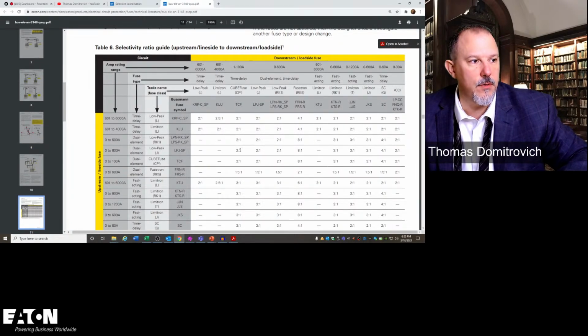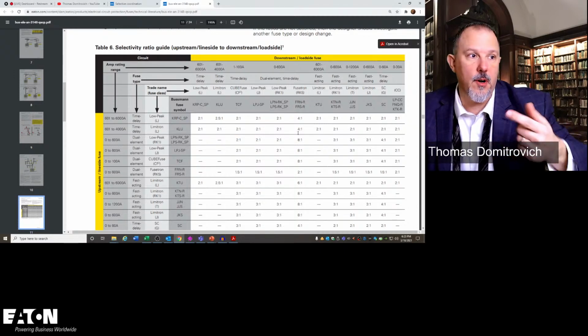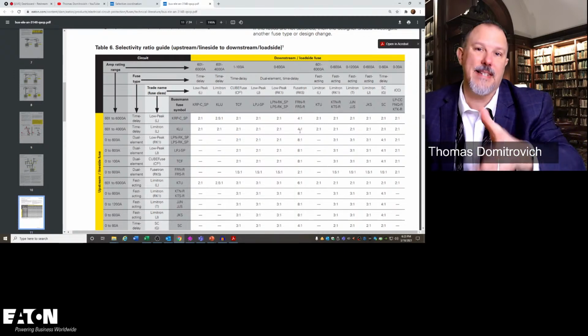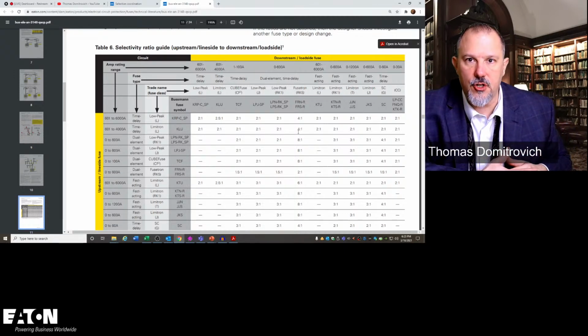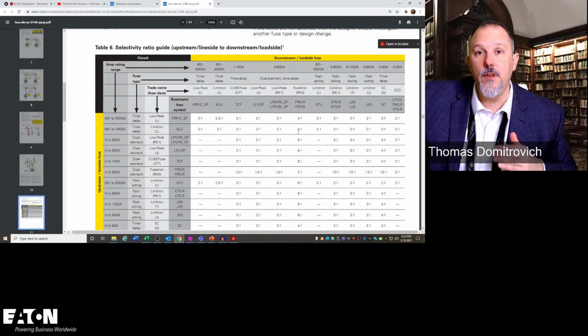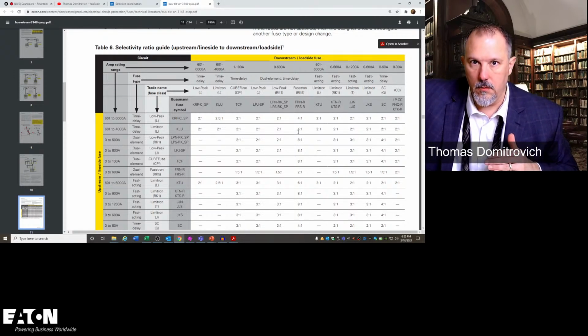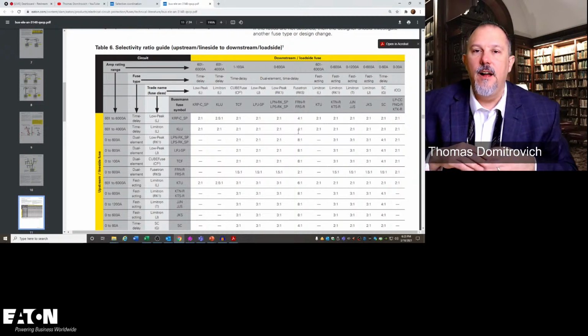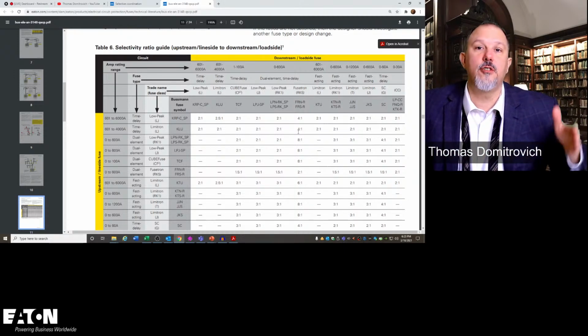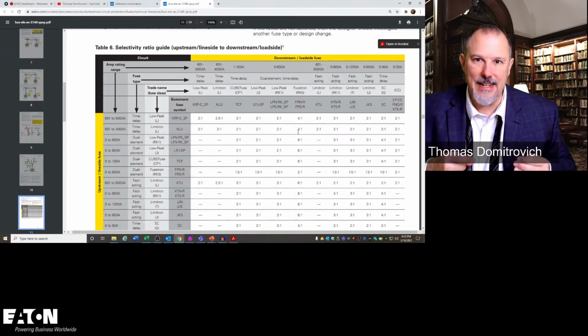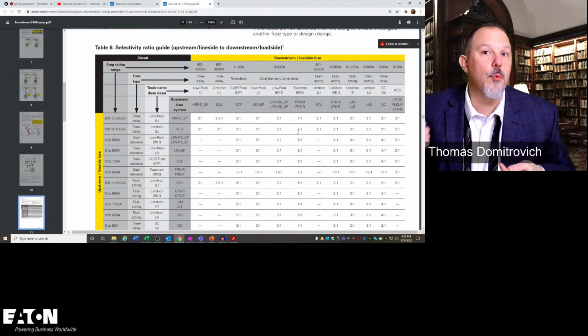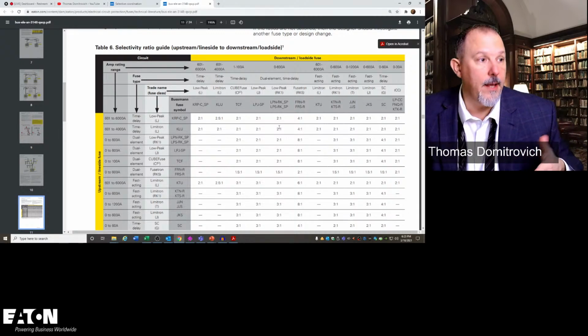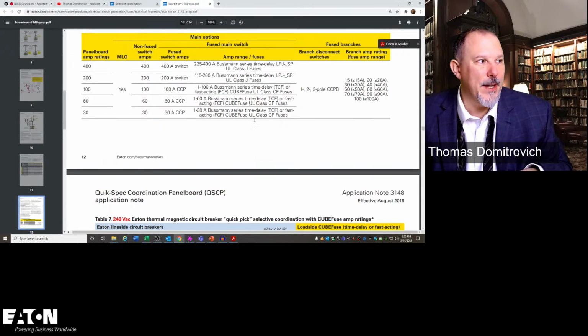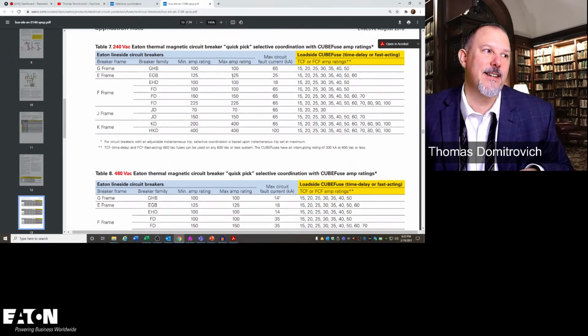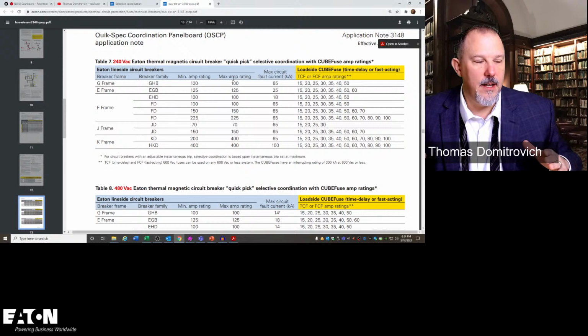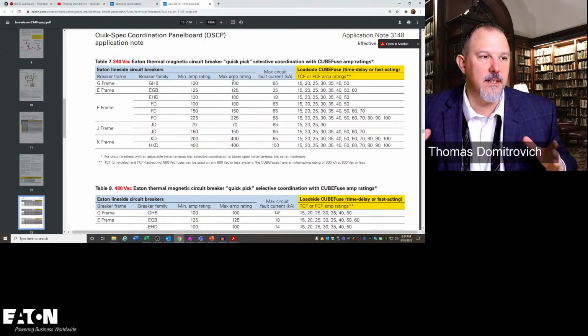Remember, so if I have a TCF fuse, there's the 2-to-1. Be mindful that depending upon the fuses that you have, it could be upwards of 8-to-1 or 4-to-1. What does that mean? If I have a 30 amp fuse downstream at a 2-to-1 ratio, as long as my upstream fuse is 60 amps or higher, the available fault current passing through both fuses could be 200,000 amps. And I will guarantee the 30 amp fuse will open and the 60 amp will not. Okay? Just because of the way the current limitation works. Here we go. Look at this. Now you are going to go, Tom, this is the silver bullet. This is the silver bullet.